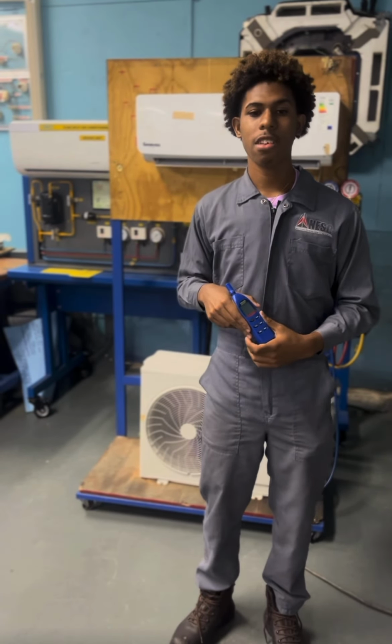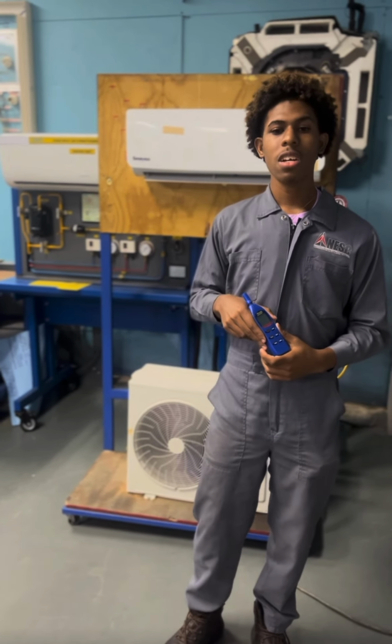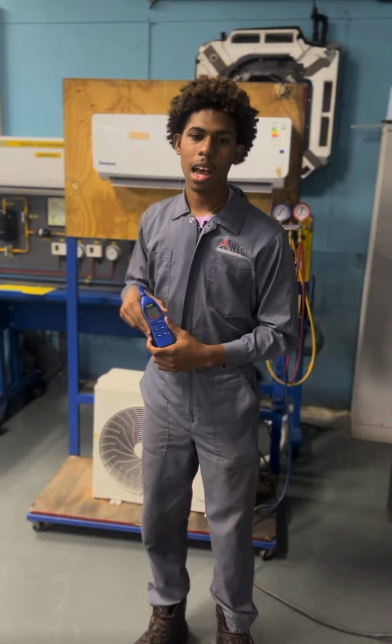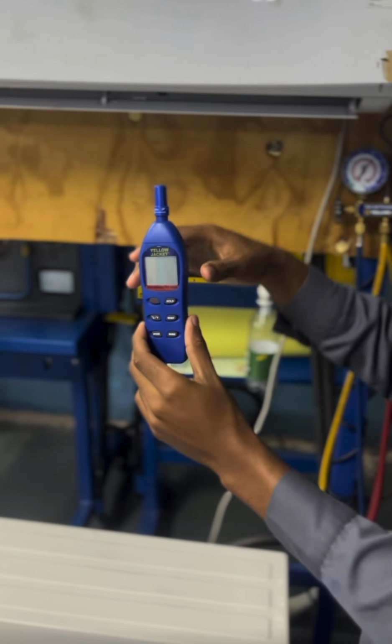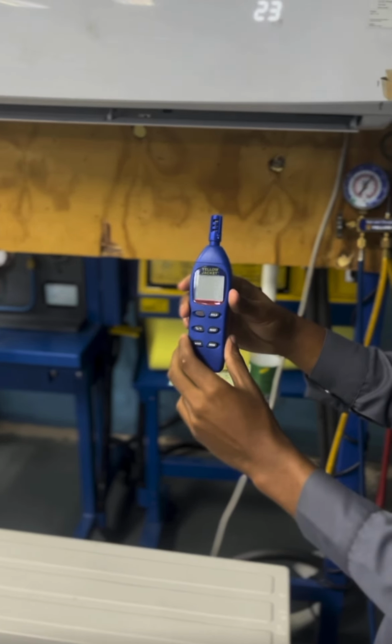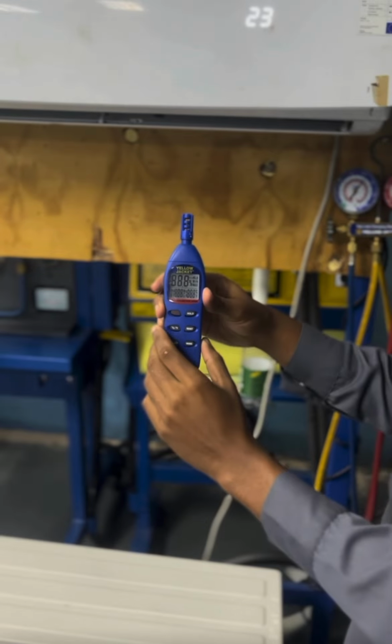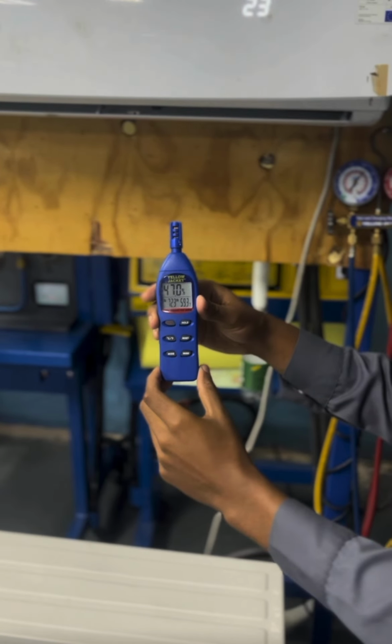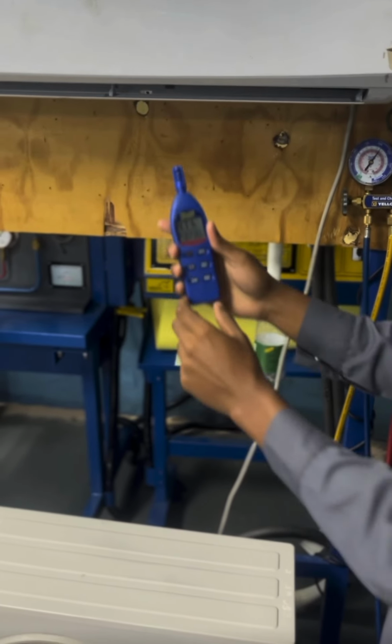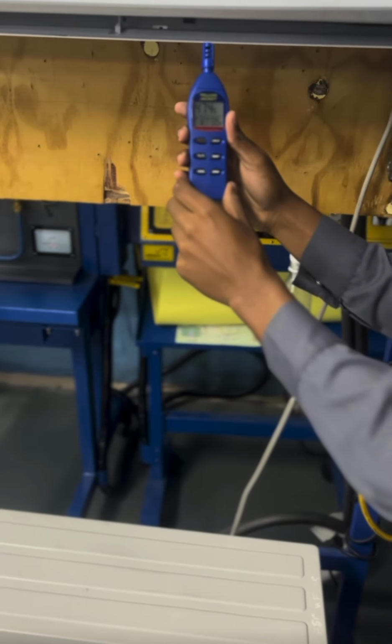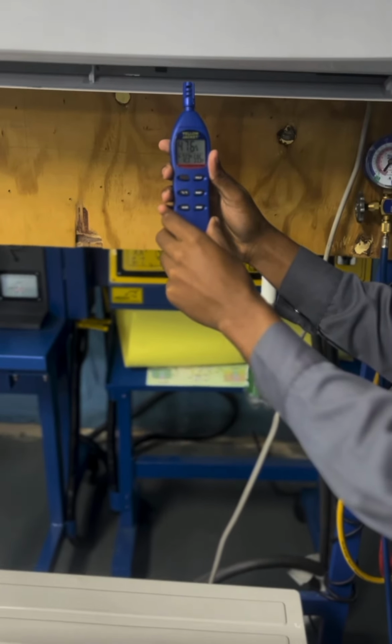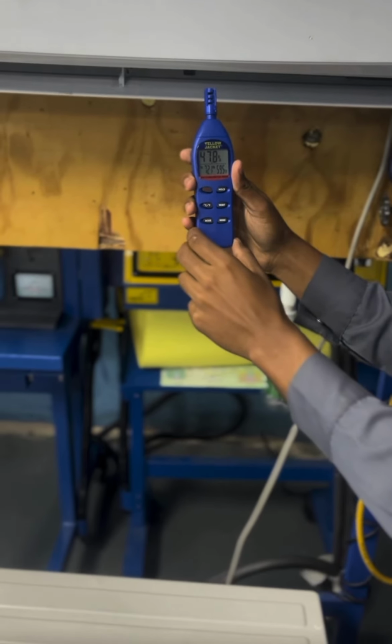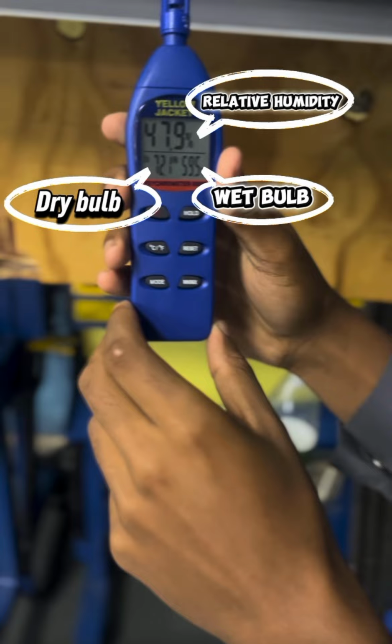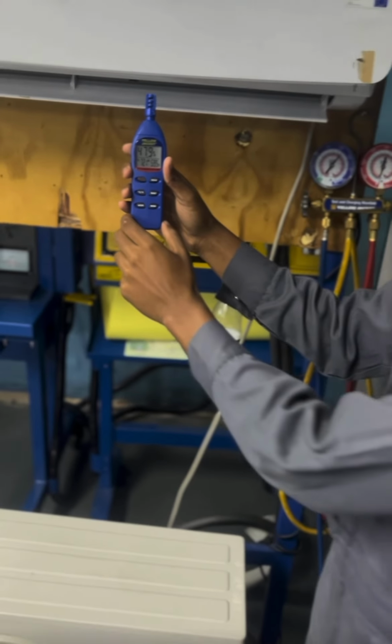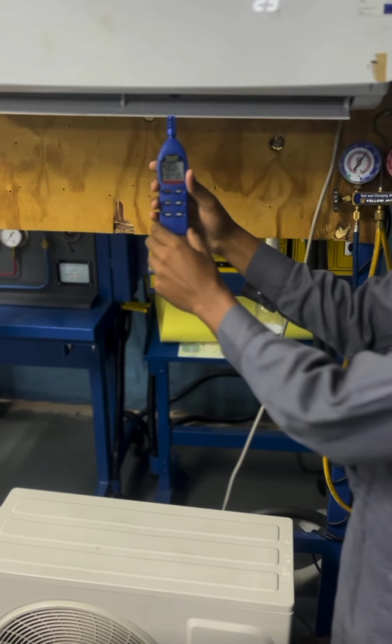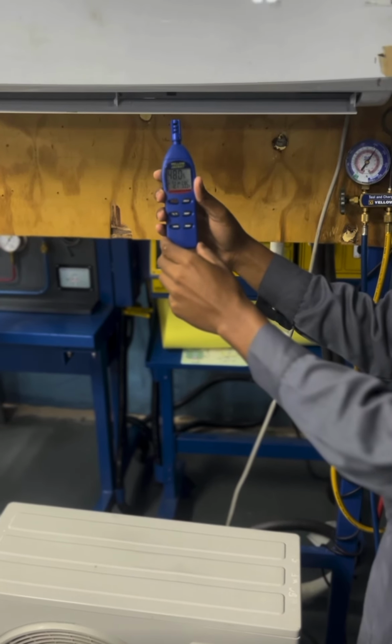Higher humidity results in a smaller temperature difference, with both readings becoming nearly equal as relative humidity approaches 100%. Firstly, remove the cap on the psychrometer. Power on the digital psychrometer, or moisten the wick for an analog unit. Place the probe or the instrument in the airstream. Allow readings to stabilize, and record dry bulb, wet bulb, and relative humidity values. Compare results with comfort standards and system design requirements, and adjust system operation if necessary.